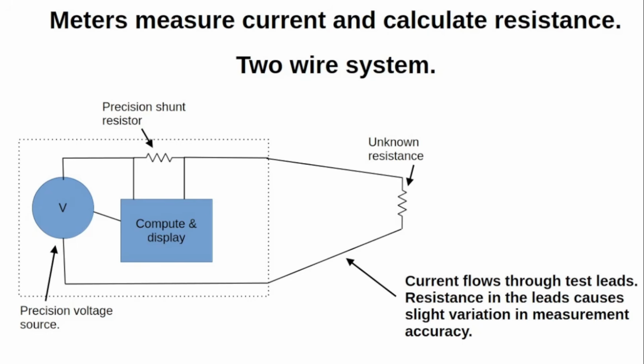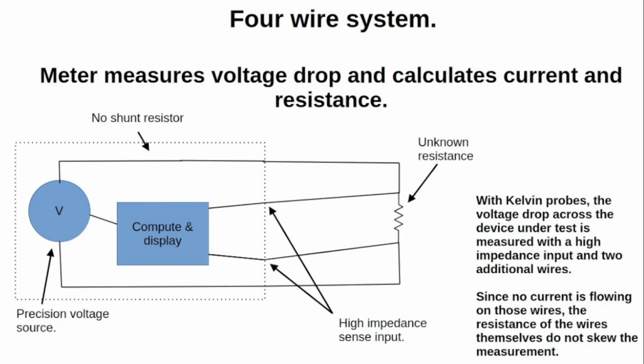So in the 4-wire system, it works a little differently. The meter still sends a voltage and current out on 2 of the wires, these feed wires, and they cause a voltage drop across the resistor. The difference is there is a second set of wires that come out and connect across the resistor, and this input on this second set of wires is a very high impedance, multi-mega ohms.